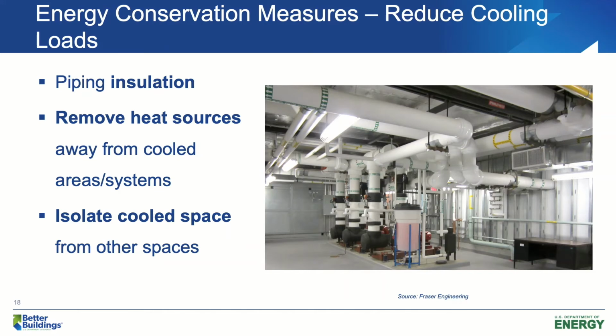The first question is, are there any damages on your piping insulation? If the answer is yes, please go ahead and get the damage fixed, because better insulation helps us to reduce the thermal loss from chilled water. The second question to ask is, are there any heat sources inside our conditioned spaces? If the answer is yes, can we remove all those heat sources? If we cannot remove them all, can we reduce the heat from those heat sources? The third question to ask is, are there any infiltration of hot and humid air into our conditioned spaces? If the answer is yes, can we do something to make our spaces sealed better? Less infiltration means less cooling load.